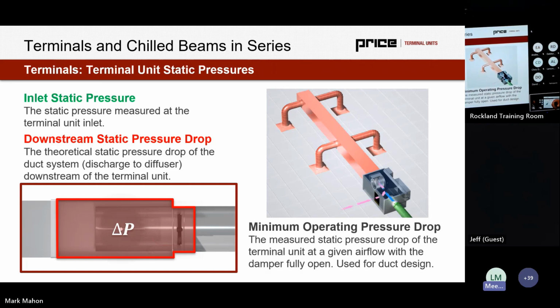unit, which tells us how much energy we have in the system to get the air delivered and mixed into the zone. We have our downstream static pressure drop, which is in red on screen here. So that is the theoretical static pressure drop of the ducted system from discharge to diffuser downstream of the terminal unit. And then we have the minimum operating pressure drop, which is the static pressure drop of the terminal at its rated airflow, assuming the damper is fully open. So that's the terminal that would be furthest away from the air handler. Therefore, we're not throttling the damper at all. It's the critical path, the longest run of duct in the system. Therefore, the damper is in a fully open position.